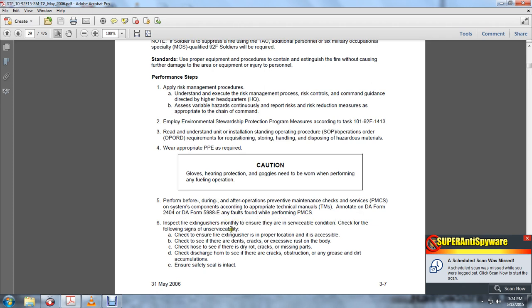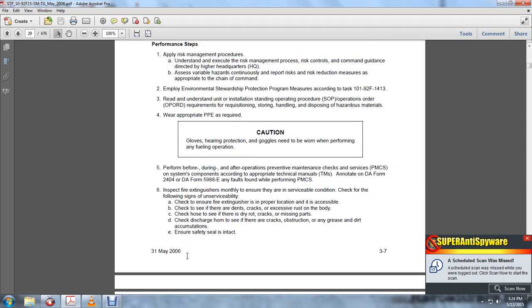Check for the following signs of unserviceability. Check to ensure the fire extinguisher is in the proper location and is accessible. Check to see that there are no dents, cracks, or excessive rust on the body. Check the hose for dry rot, cracks, and missing parts, and check the discharge horn for cracks, obstruction, grease, or dirt accumulations. Ensure the safety seal is intact. Ensure the pressure gauge, if so equipped, is in the green, fully charged. Ensure the operating instructions are visible and readable.